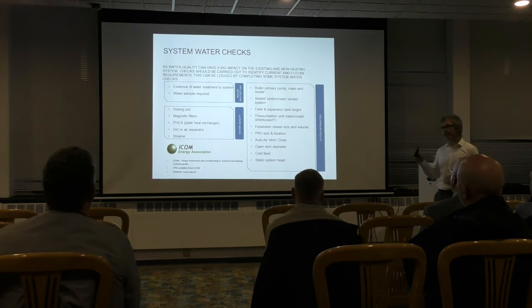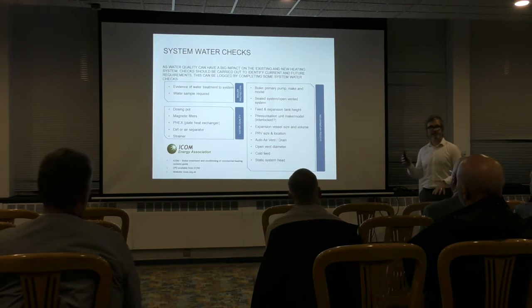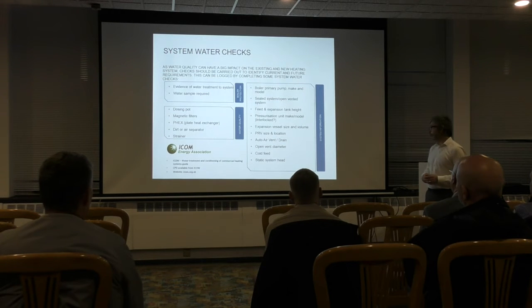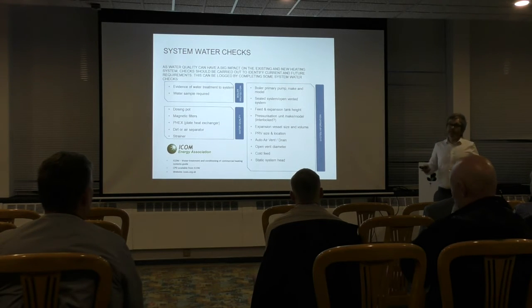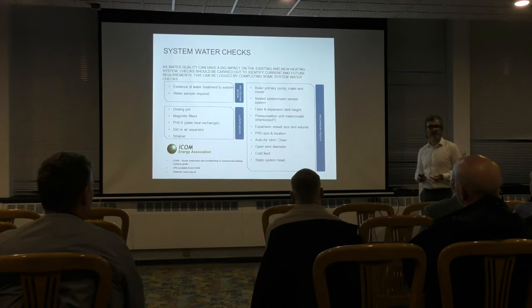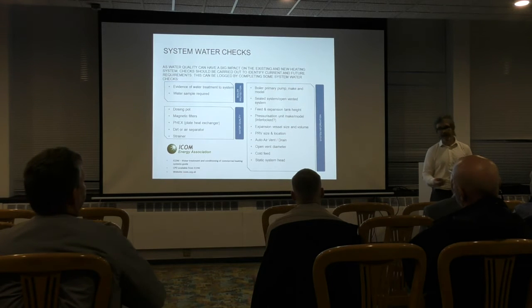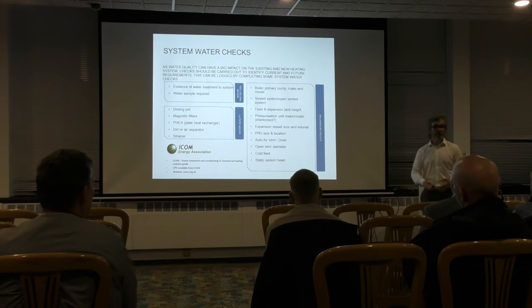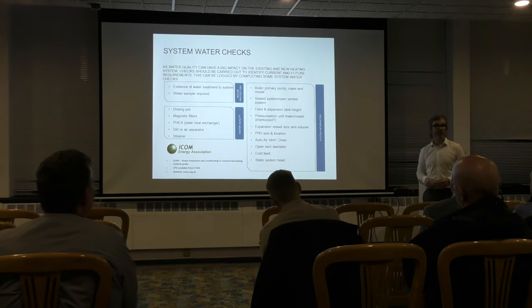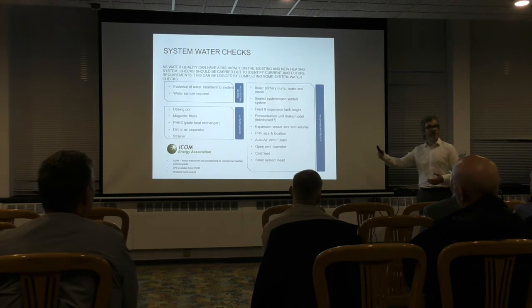When we're looking at a tall building and your boilers are in the basement, potentially you could have quite a lot of pressure on the boilers. So that's not an issue, because there's two ways around that. You either find a boiler that can withstand that pressure, again, that can really narrow down your boiler selection, or put in a plate heat exchanger. Because if you put a plate in, your boilers will be sitting there working at 2.5, 3 bar, where the rest of your system could be on 10 bar, or as in your secondary side.